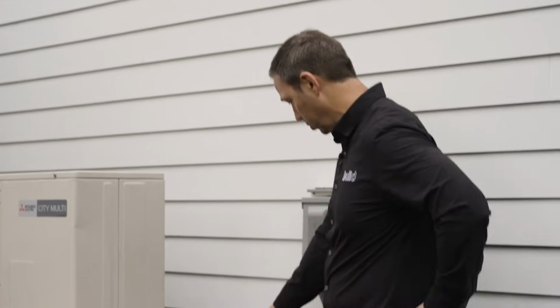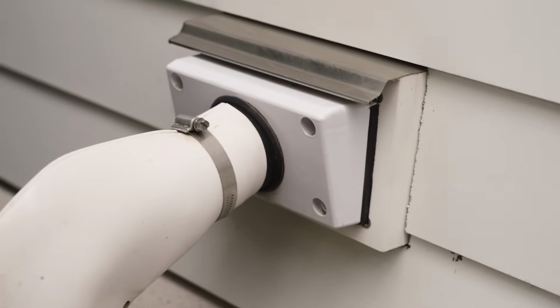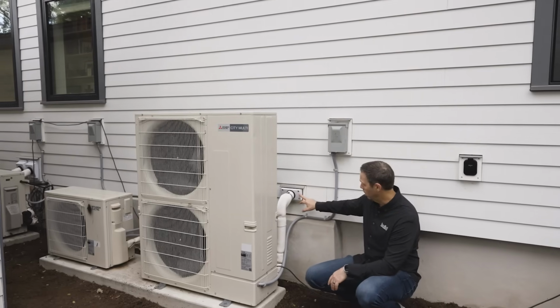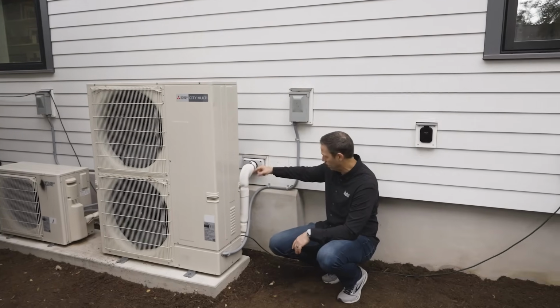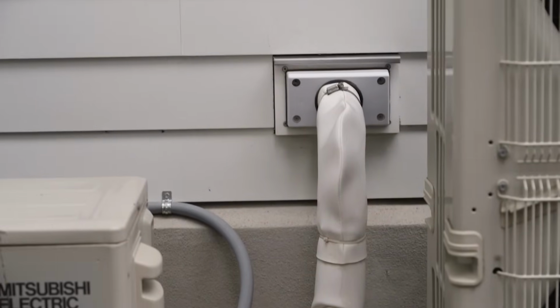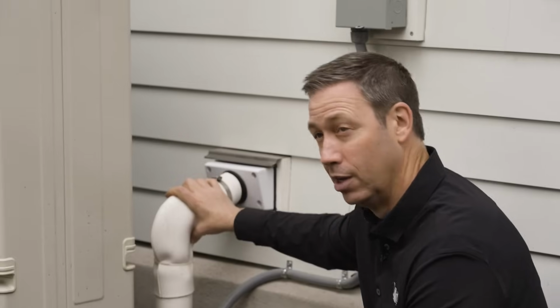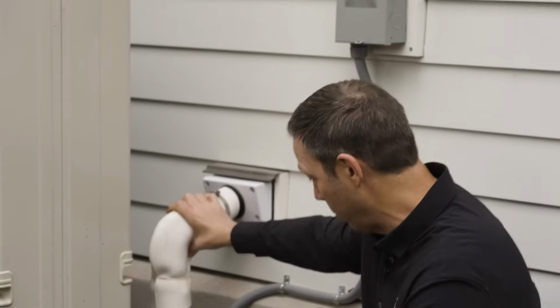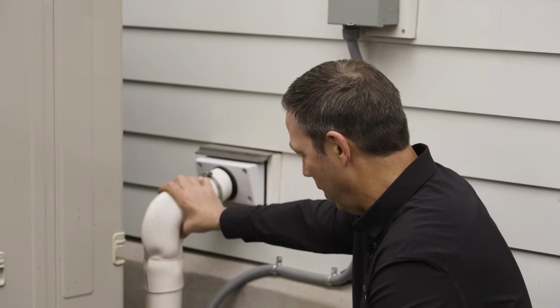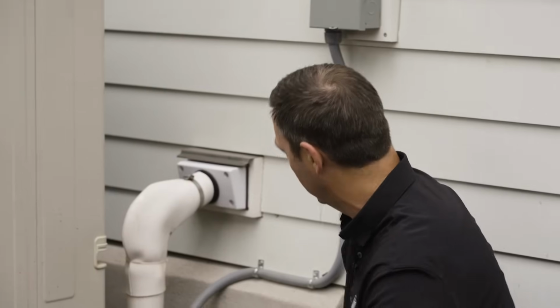And then check this out. This is my Airex Titan outlet. I can't remember the name. I think this might be the TSS model. They have several different models. This is the smaller unit, which you can see the pipe that comes out, the Freon line, totally protected by this PVC here. So in other words, all the pipe insulation is covered by their PVC, which means no degradation. Now my white PVC is a little dirty after being out in the rain for 2 years. But other than that, no degradation, looks fantastic. I can feel my insulation in there still in perfect shape.